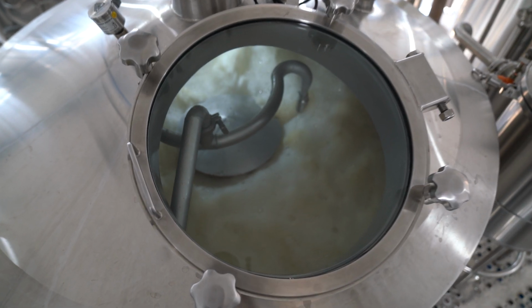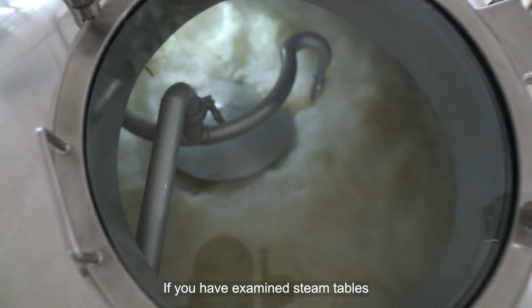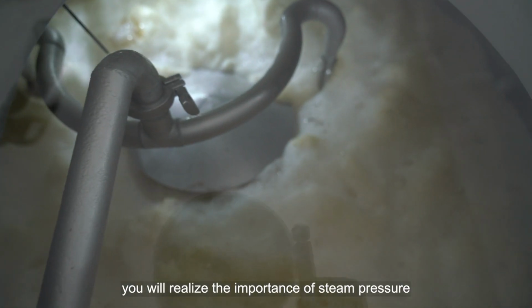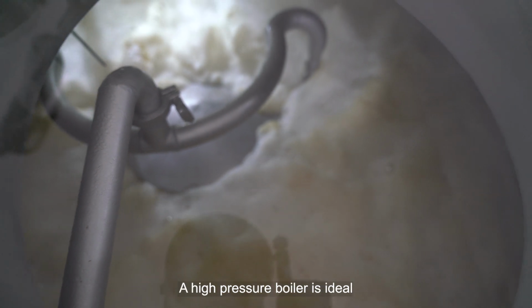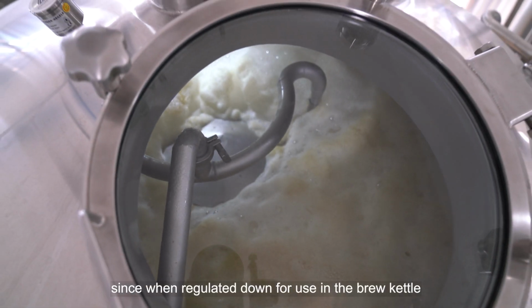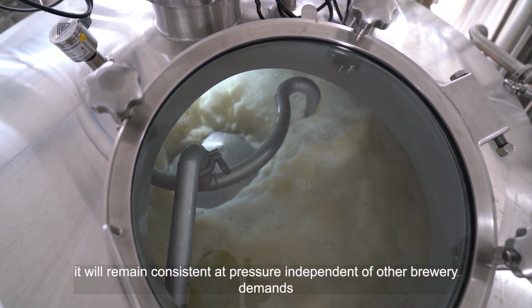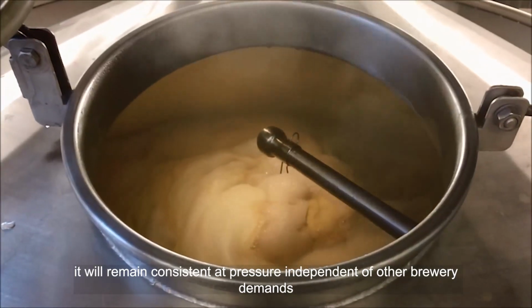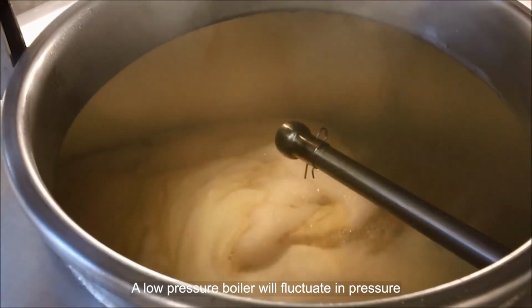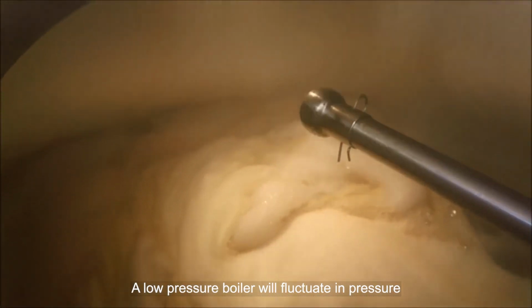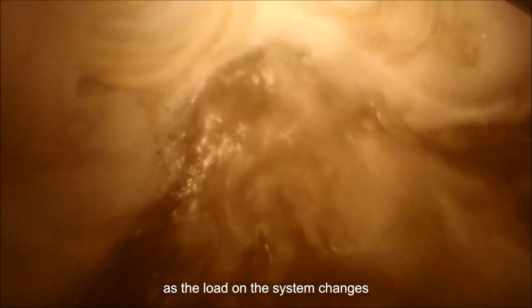Steam pressure. If you have examined steam tables, you will realize the importance of steam pressure and its relationship to temperature. A high-pressure boiler is ideal, since when regulated down for use in the brew kettle, it will remain consistent at pressure independent of other brewery demands. A low-pressure boiler will fluctuate in pressure as the load on the system changes.